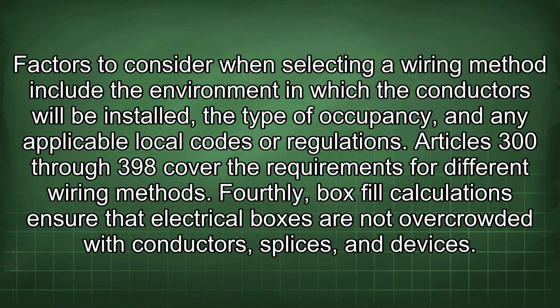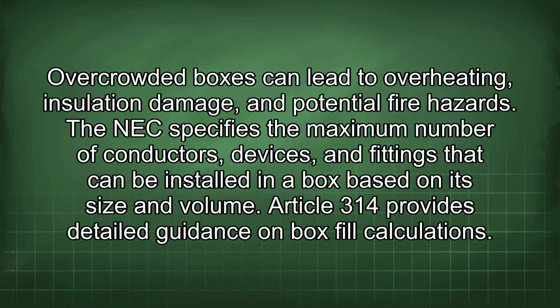Fourthly, box fill calculations ensure that electrical boxes are not overcrowded with conductors, splices, and devices. Overcrowded boxes can lead to overheating, insulation damage, and potential fire hazards. The NEC specifies the maximum number of conductors, devices, and fittings that can be installed in a box based on its size and volume. Article 314 provides detailed guidance on box fill calculations.